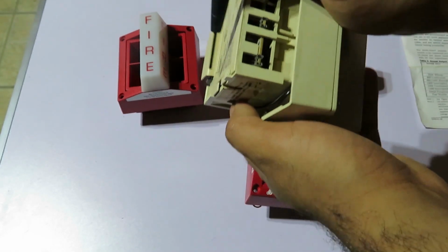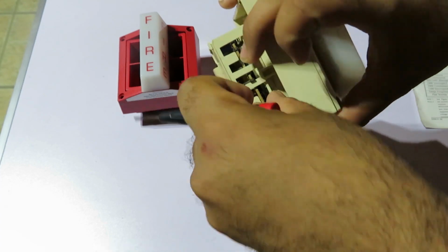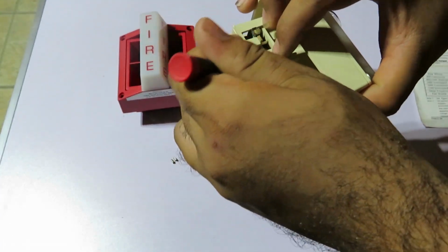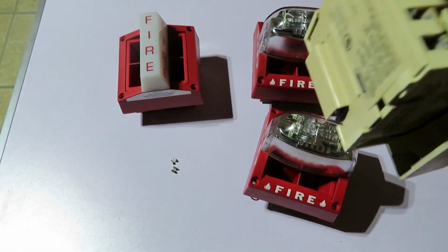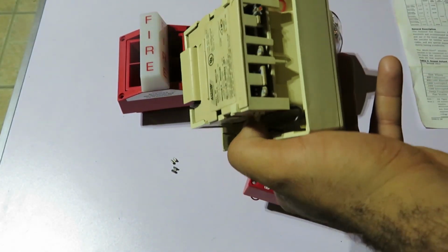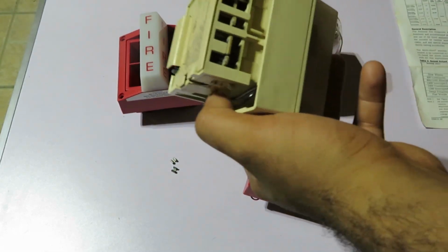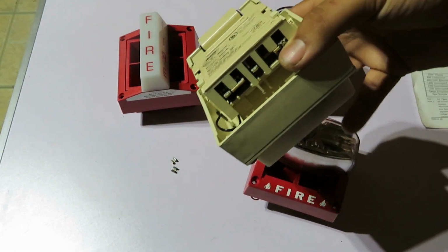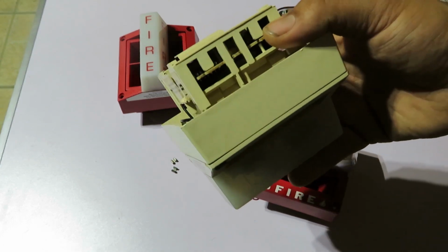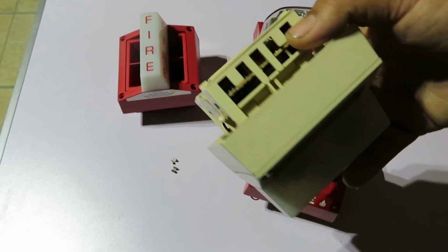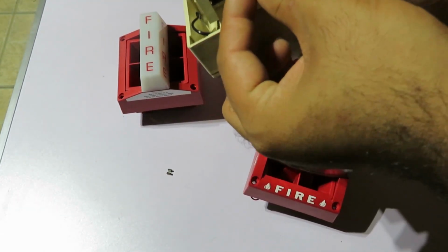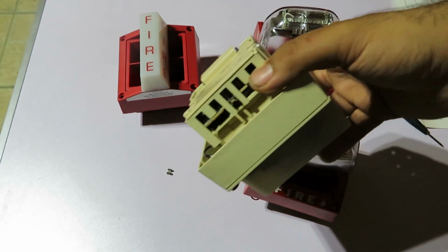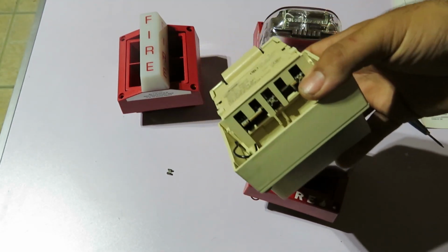What you need is a flat screwdriver, and if you want to change the tone, you can pry it off and do whatever you wish. And like I said with this picture, take a look, figure out what tone you want, and you're good to go. So pretty much in this configuration, the tone will be 2400 Hz continuous, which I'm not in favor of, so I'm just going to go ahead and put this back in. But yeah, that's pretty much how you change the tone on a MASS series.